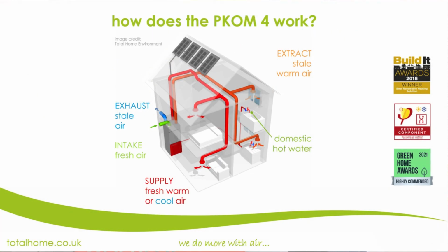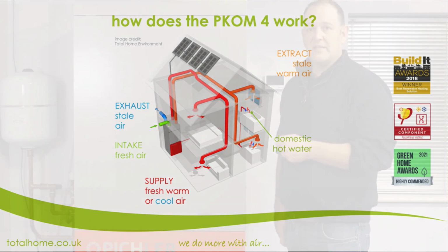The heat recovery system is a very efficient heat exchanger inside. It will extract about 90% of the heat from the outward going air. The outward going air is an extract from your bathroom and your kitchen, and that heat is then passed to the fresh filtered air that is coming from the outside, where any pollen and particulates have been taken out by the filter before it heads off into the property.